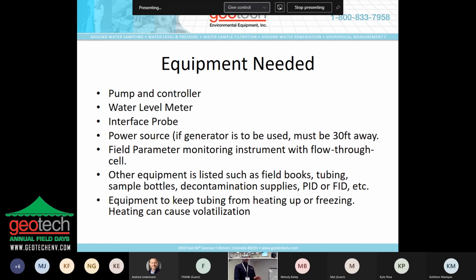One thing I don't have on here that's also great to have is a Y valve, because you never want to sample post flow cell. Flow cells are commonly plastic and metal with O-rings and nooks and crannies that are hard to decontaminate. So you don't want to get your sample post flow cell. Having a T valve or a Y valve pre-flow cell that you can get your sample from is really key, actually. So keep in mind that that's another addition you'd probably want.